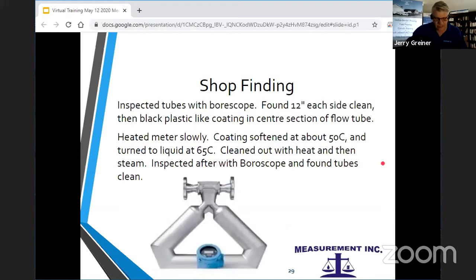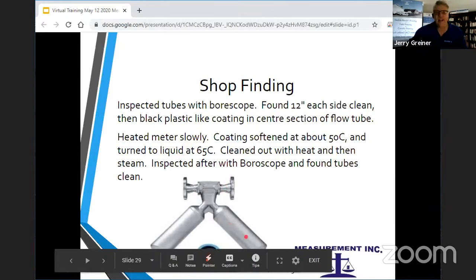So what we did then is we put a borescope through, and we found that there was about 12 inches clean on each side. In this meter, which was a triangular shape, there's 12 inches of clean, and then it went to a black plastic coating. It just looked as though it was painted. And the bottom section was totally coated with a black plastic coating.